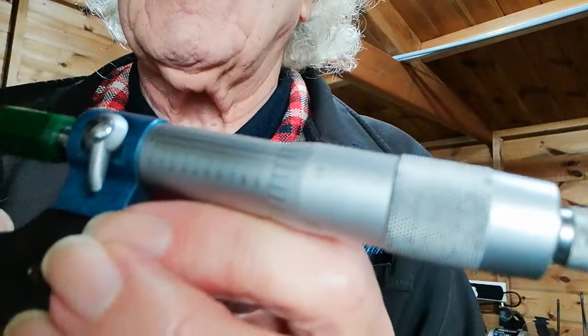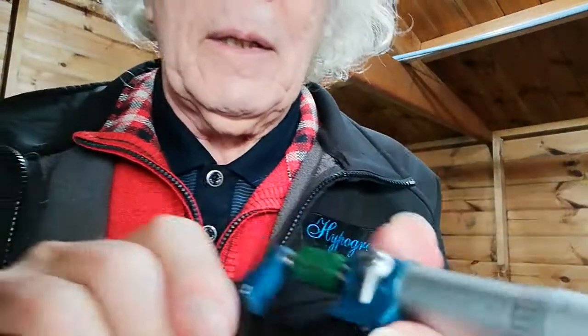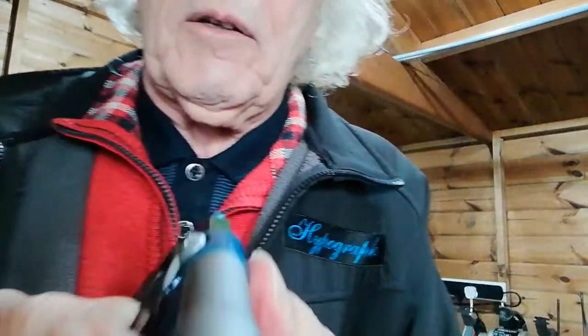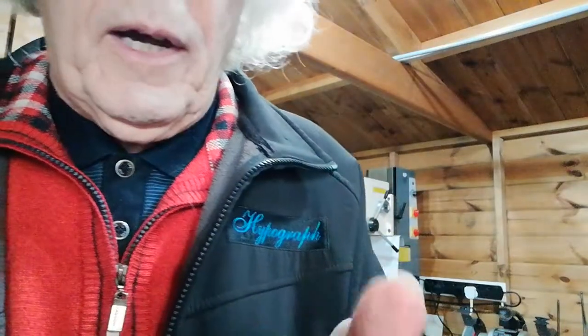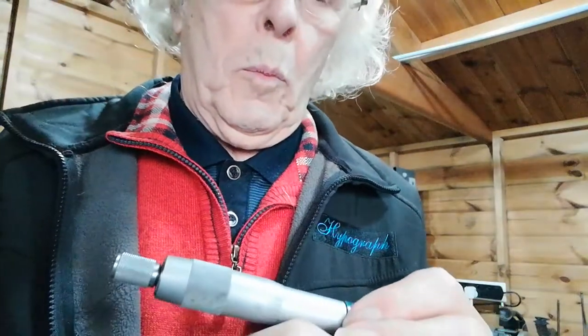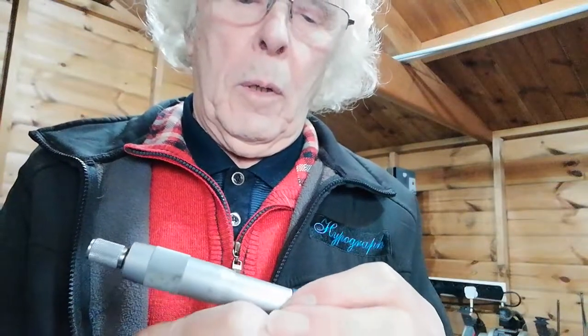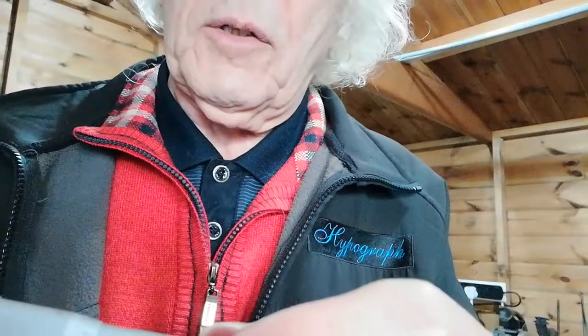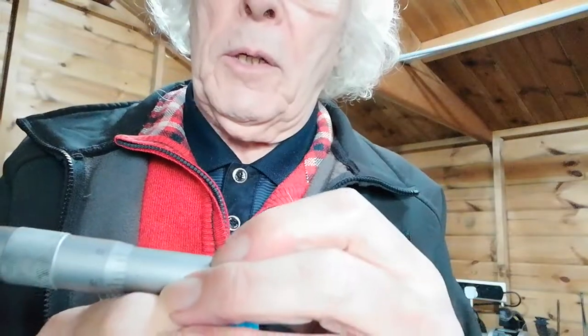Wow. That's a 0, not quite on the line. So when I look at it, I think it's about 2 or 3 thousandths of an inch out actually. And I can tell that by checking the other graduation marks, when they line up on a number there, which are numbered 1 to 0, and the one that's nearest on the graduations is number 3. Can you see it?